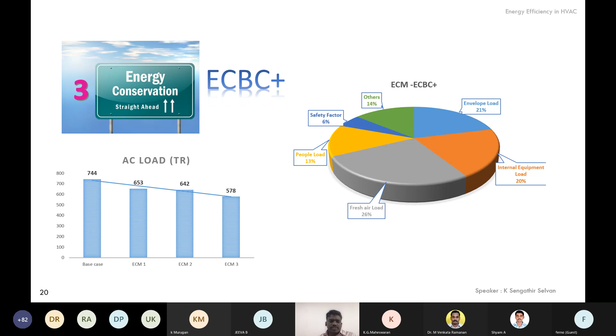So what are the next big opportunities? Now we have seen that by working out different options in the envelope, we could reduce the heat load from 744 to 578. This is approximately 600 and around 160 TR, and 160 TR is around 25% that we have reduced only by working on the envelope. Now, what is the next big opportunity?